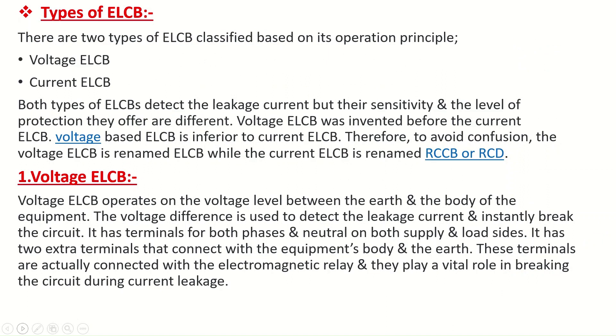Types of ELCB. There are two types of ELCB classified based on their operating principle: Voltage ELCB and Current ELCB. Both types detect leakage current, but their sensitivity and level of protection differ. Voltage ELCB was invented before Current ELCB and is considered inferior. To avoid confusion, Voltage ELCB is now referred to as ELCB, while Current ELCB is renamed RCCB or RCD.